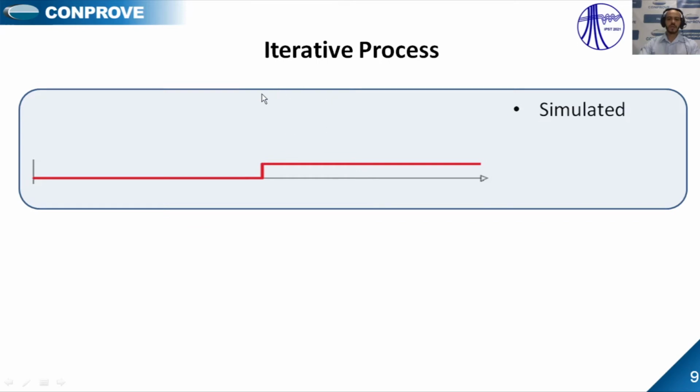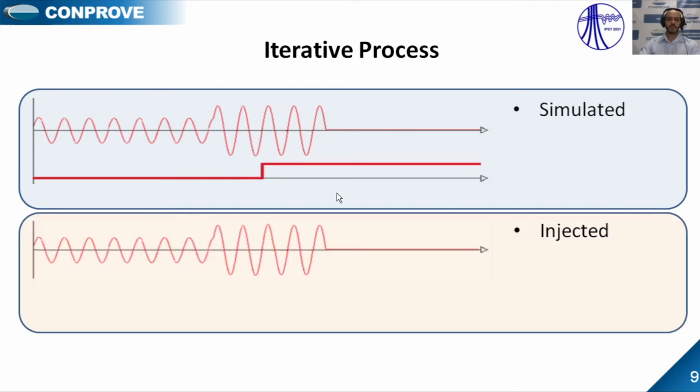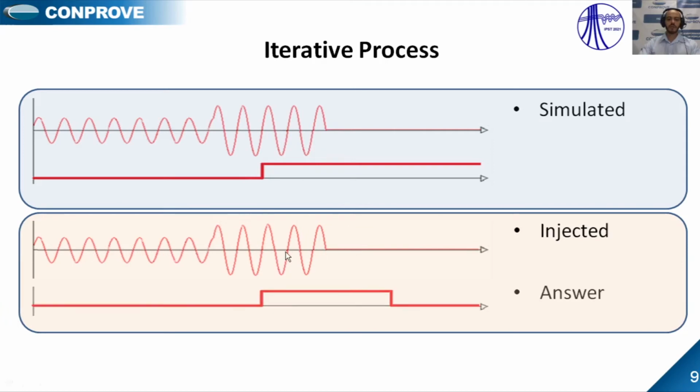And the next step, the new simulator will be changed from the first one, because now we have the circuit breaker opening with the modeling, with the time that is inside of the modeling. And then the last one, the last waveform is injected and the answer of the IED opening the circuit breaker, and here it's going down because the current is not present anymore. And the last injected signal is the same as a real-time simulator.